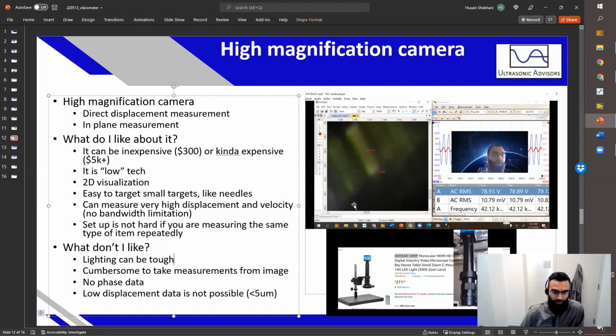Just like draw a line and do conversions. There's no phase data, and you can't do low displacement measurements. Sometimes it's convenient to use lower voltages to start off with, but you can't do that. And as you increase your amplitude, you'll increase your ability to measure more accurate data. So measuring the 10 to 20 micron range is not going to be near as accurate as the 100 to 110 micron range. That's going to be much more accurate percentage-wise if you're measuring a larger signal, which is very problematic if you're doing high frequency devices.